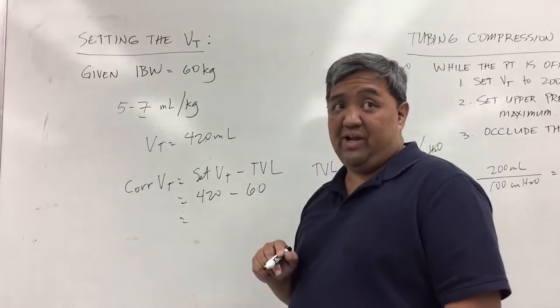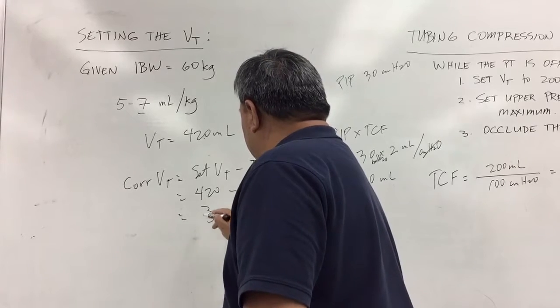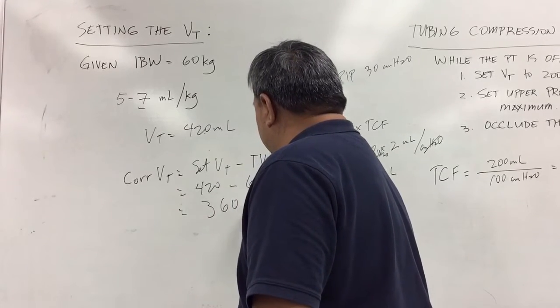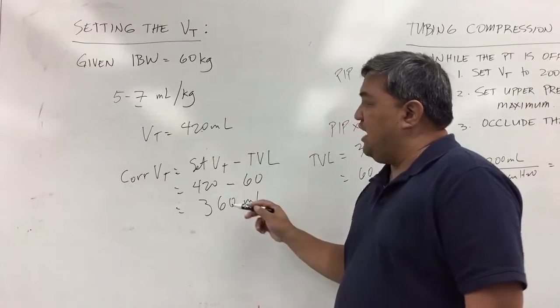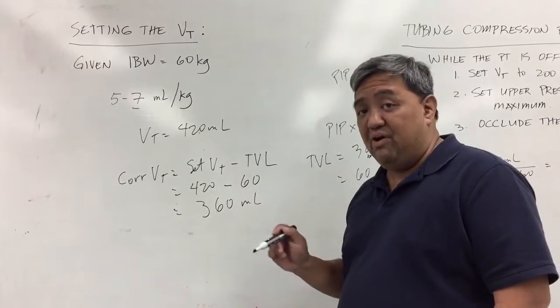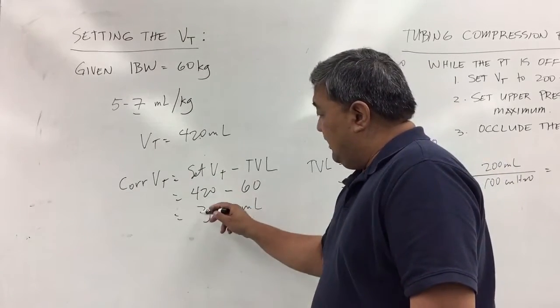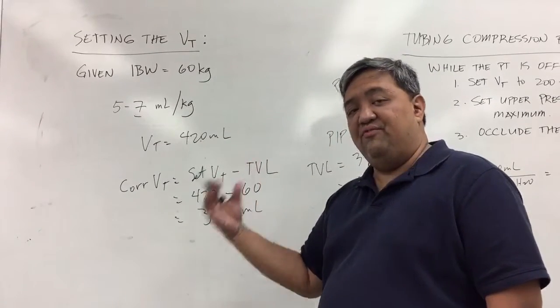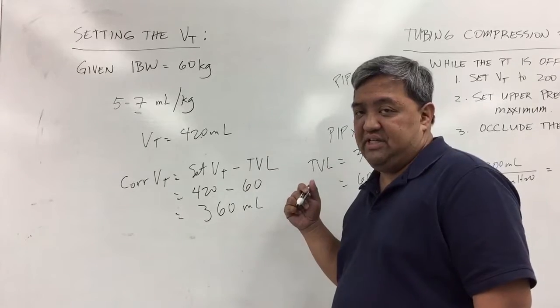If I do my math correctly, that's 360 mls. So that means the volume being received by the patient is 360 mls. However, once you have a ventilator that does not compensate for the TCF...